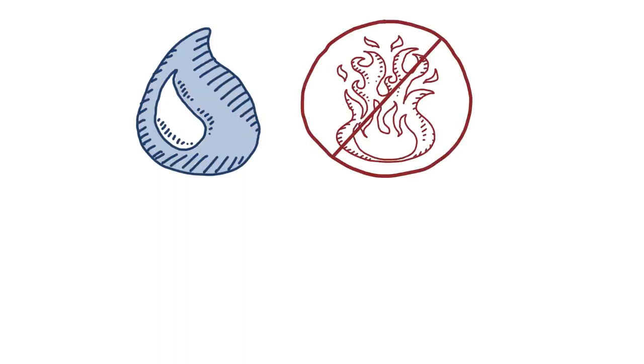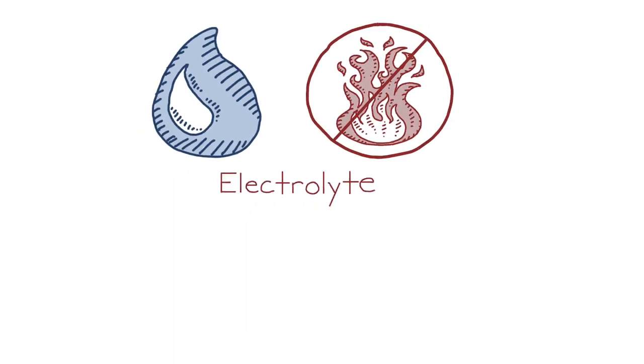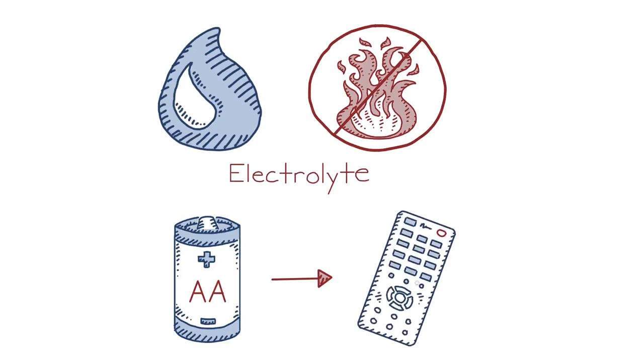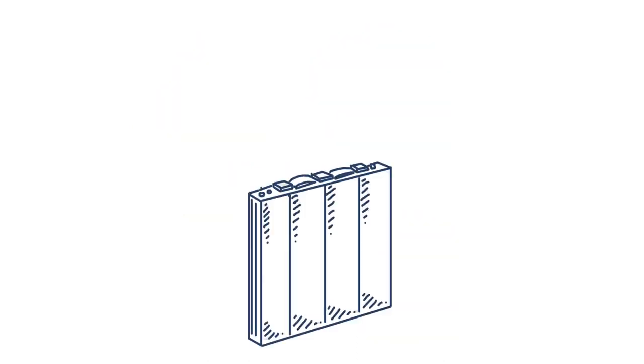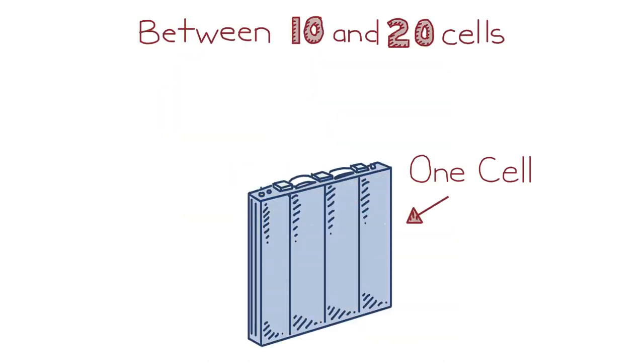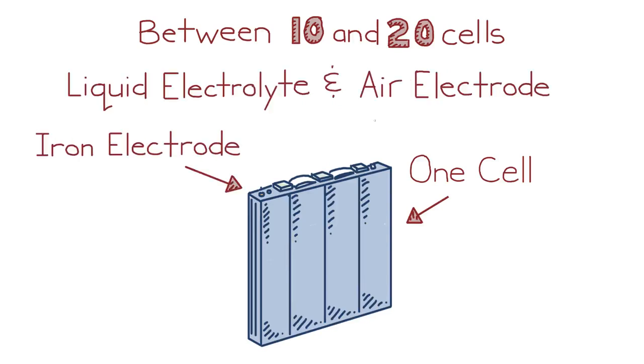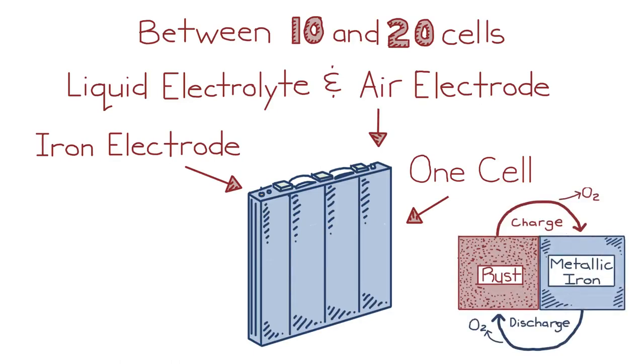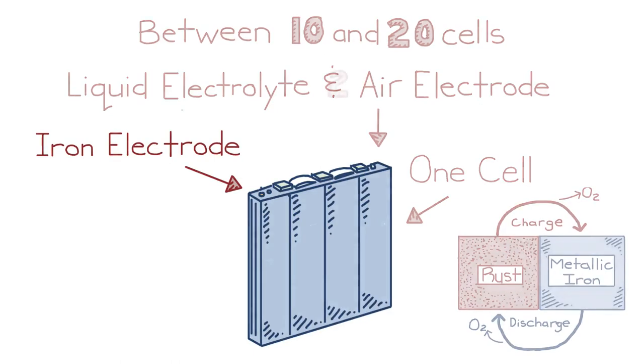Taking an even closer look inside the battery, each one is filled with a water-based, non-flammable electrolyte like those used in the AA batteries in your TV remote. Inside the battery are stacks of anywhere between 10 and 20 cells, which each include an iron electrode, the liquid electrolyte, and an air electrode, the parts of the battery that conduct and carry electricity on charge and discharge.